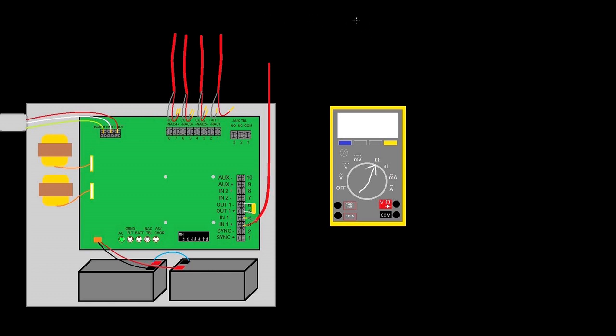Let's say as you're going across you get a few different readings. Let's say the first reading you get is 3.2 megaohms. You get a few other readings on some of the other circuits, maybe you get some OLs.